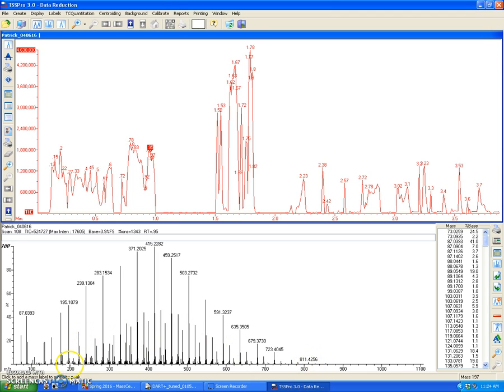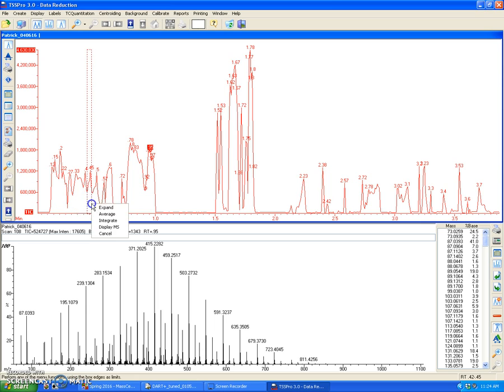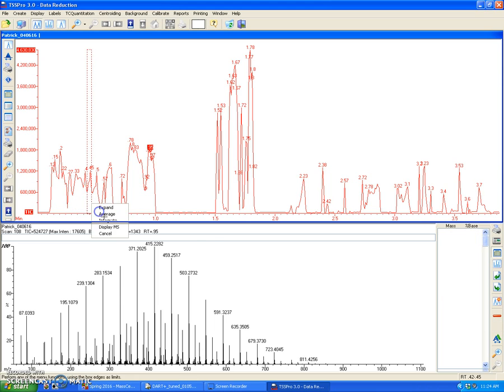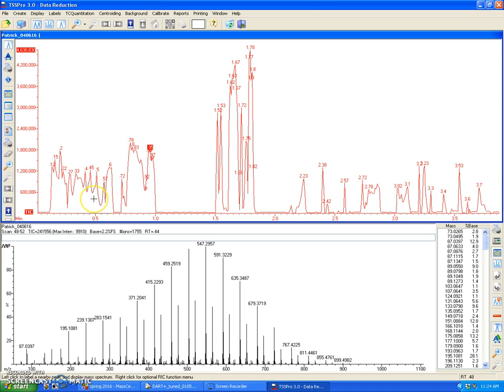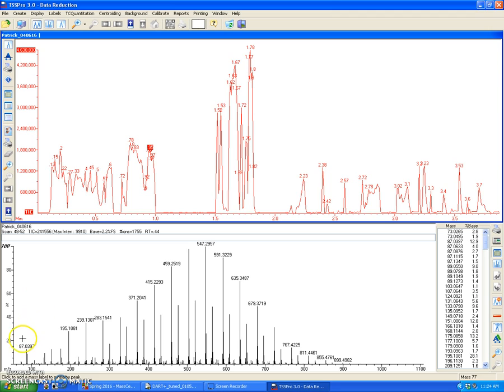So if I'm interested in the 200 to 600 region, I would choose this mass spectrum to calibrate against. If I were focusing on the 300 to 700 region, I would choose this. So what you're going to have to do is average a specific region to where you have the highest ion intensities of where your analytes will be. If you have a broad range of analytes, you can just choose a mass spectrum that covers the full distribution.